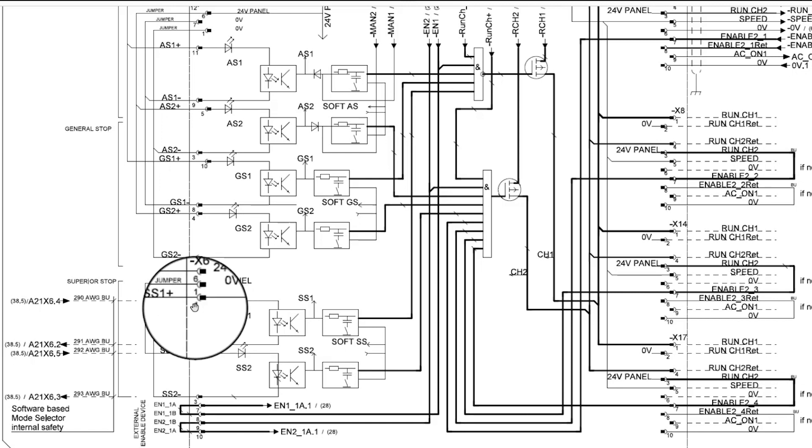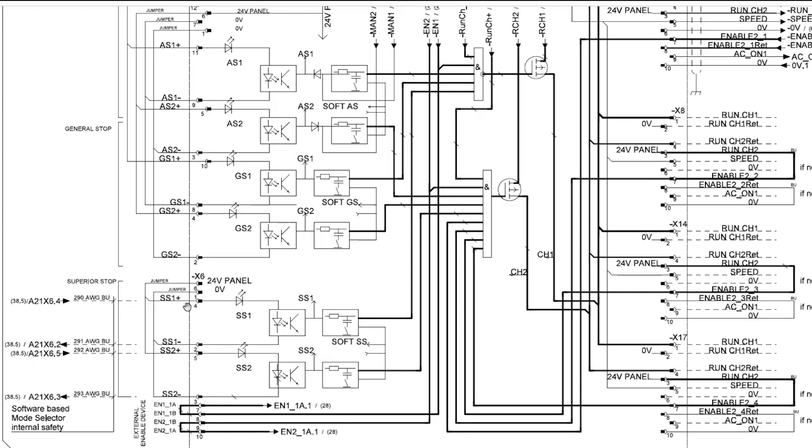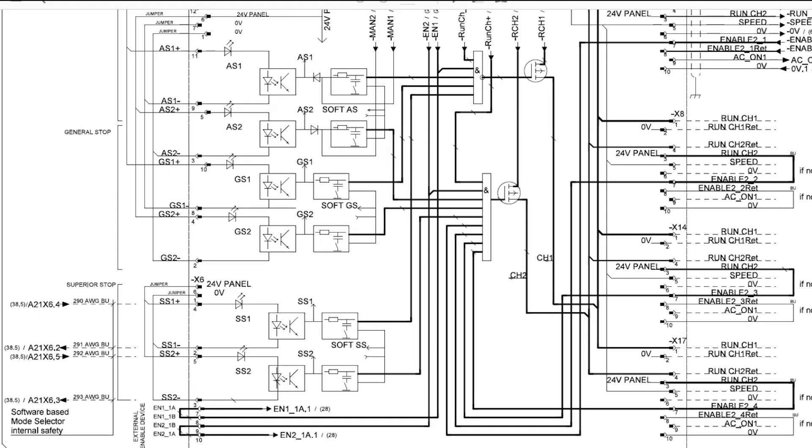Our superior stop safety chain is a dual channel chain which requires each channel to be broken at the exact same time. If the SS1 channel is broken before the SS2 channel, then the controller will provide a fault in reference to inconsistent timing of signals.